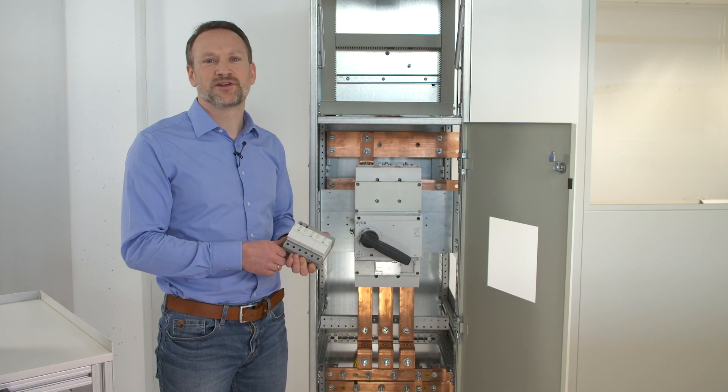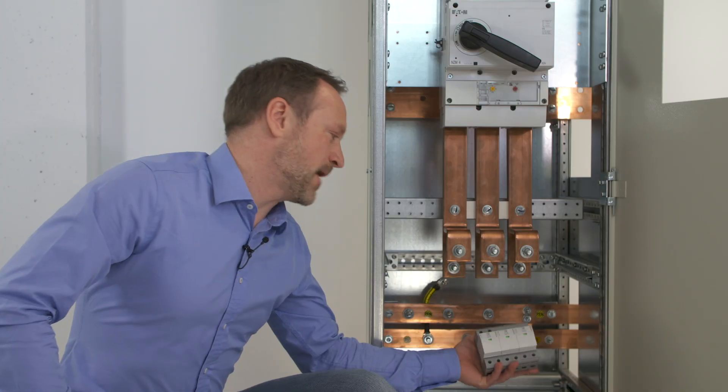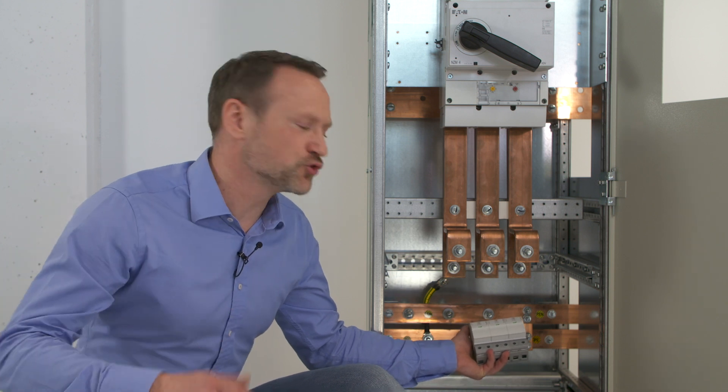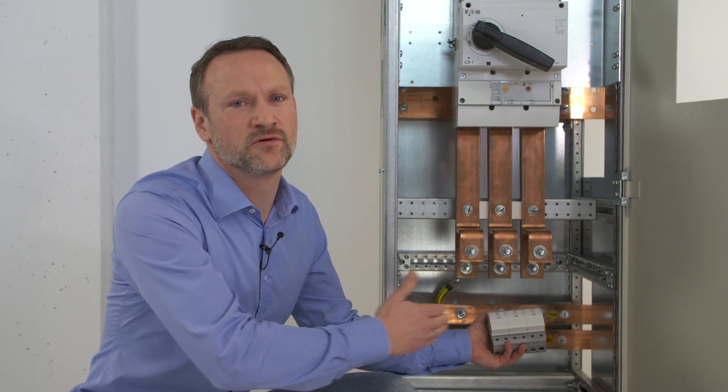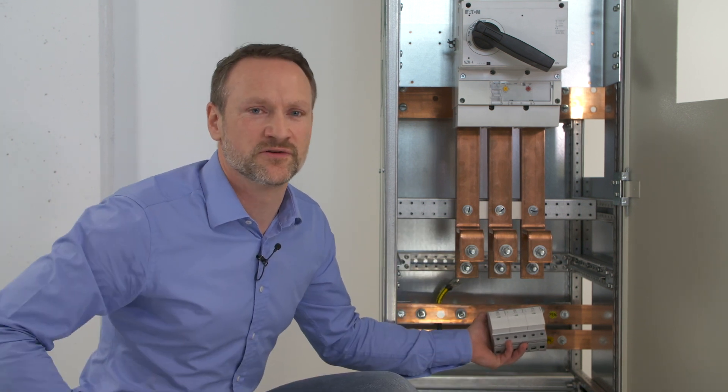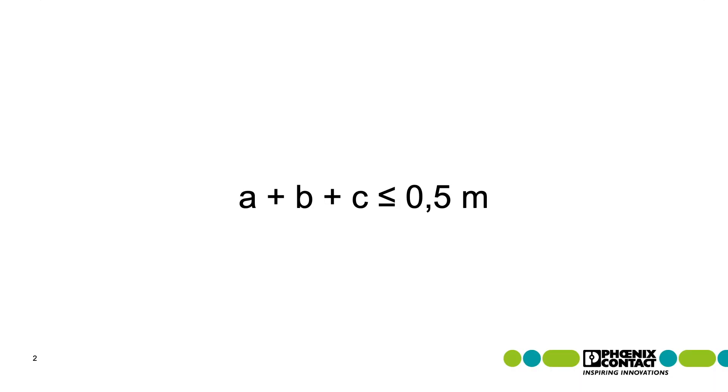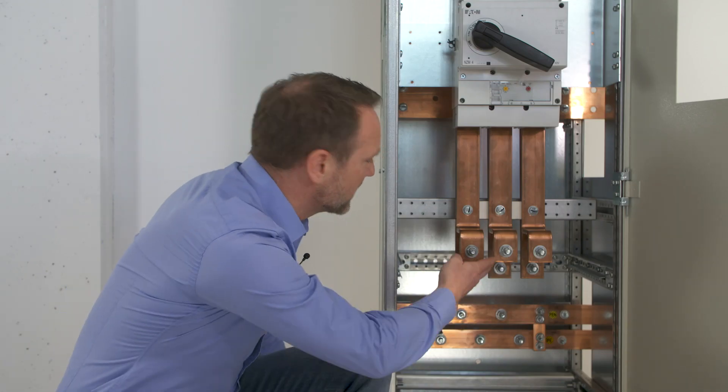But how can we solve this cable length problem? If we installed the protective device in the lower area of the control cabinet, the cables would be much shorter already. However, taking the cables to the backup fuse, the protective device and the connections into account, it would still be too long as the standard requires a connection length shorter than 50 cm. Not to mention the fact that we do not have the space to house the backup fuse here correctly.